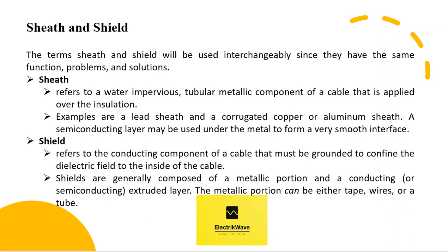Shield refers to the conducting component of a cable that must be grounded to confine the dielectric field to the inside of the cable. Shields are generally composed of a metallic portion and a conducting or semi-conducting extruded layer. The metallic portion can be either tape, wires, or a tube.